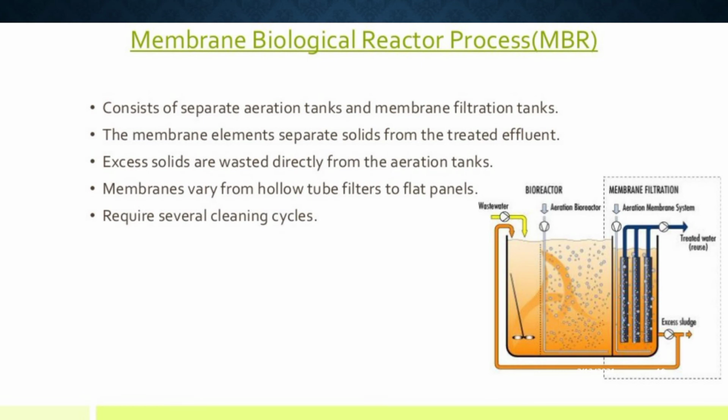Now next is membrane biological reactor process, MBR. It consists of separate aeration tanks and membrane filtration tanks. The membrane elements separate solids from the treated effluents. Excess solids are wasted directly from the aeration tanks. Membranes vary from hollow tube filters to flat panels. It requires several cleaning cycles.